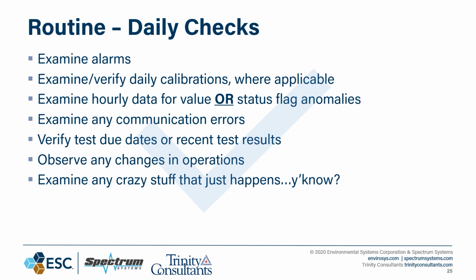Look for things like, on a dry extractive system, take a look at the peristaltic pump. Make sure that there's not a lot of moisture building up or backing up into the AC unit. Very simple visual checks that take 30 seconds to do could save you a lot of time or even operational downtime.